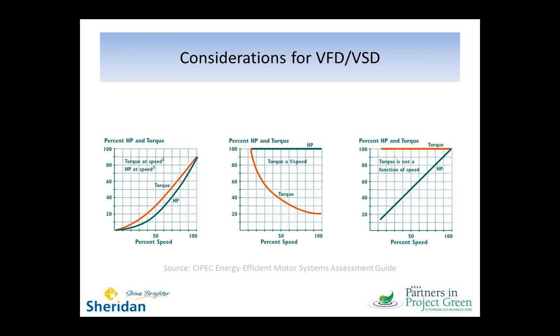The second, what I've got here, is a constant power load. So as my speed is dropping, my torque is actually increasing. This is the kind of load we're going to see on milling machines, lathes, drills. And this is not an application where a variable speed drive is actually going to do anything. What you need here is a specialized constant horsepower motor that's able to handle the higher torque requirement at lower speed. And a variable speed drive is probably not going to work in this application.